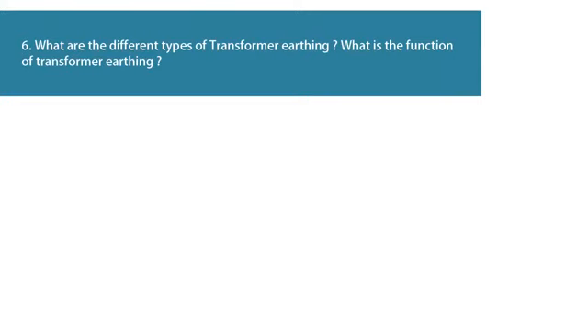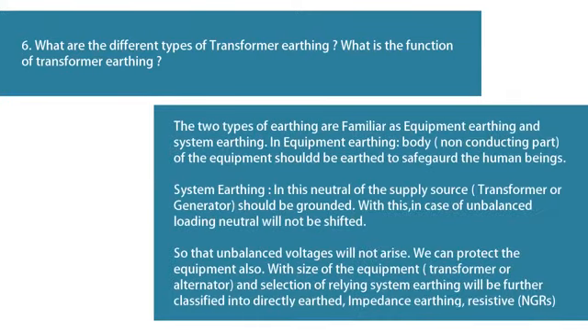Question 6: What are the different types of transformer earthing and what is its function? The two types of earthing are equipment earthing and system earthing. In equipment earthing, the body and non-conducting parts of the equipment should be earthed to safeguard human beings. In system earthing, the neutral of the supply source — transformer or generator — should be grounded so that in case of unbalanced loading, the neutral will not be shifted and unbalanced voltages will not arise. Depending on the size of the equipment and selection of the relay system, earthing is further classified into directly earthed, impedance earthing, resistive earthing (NGRs).